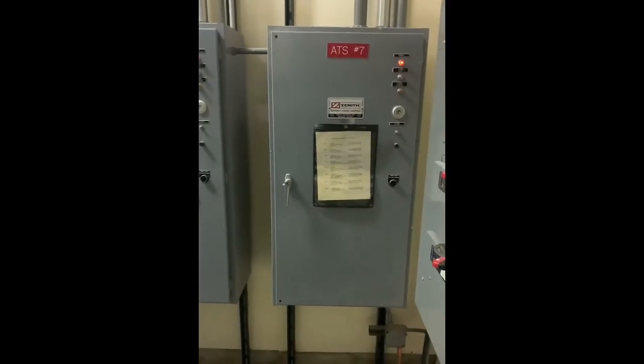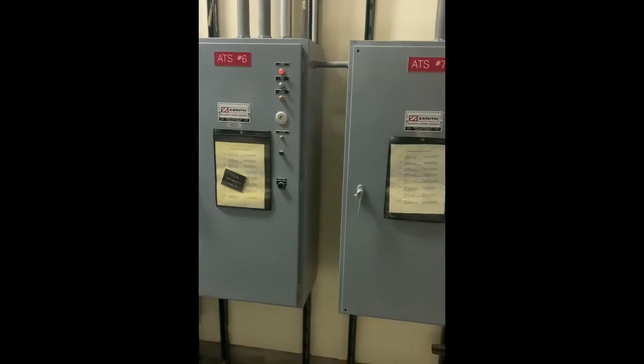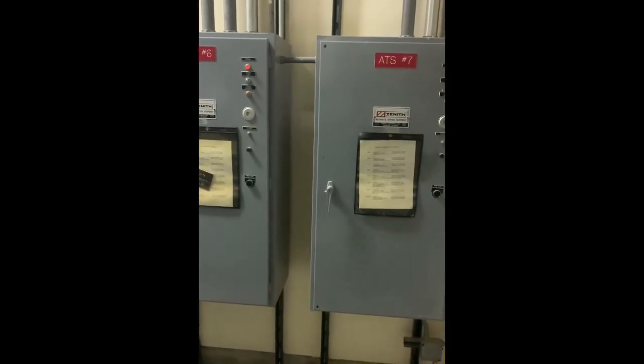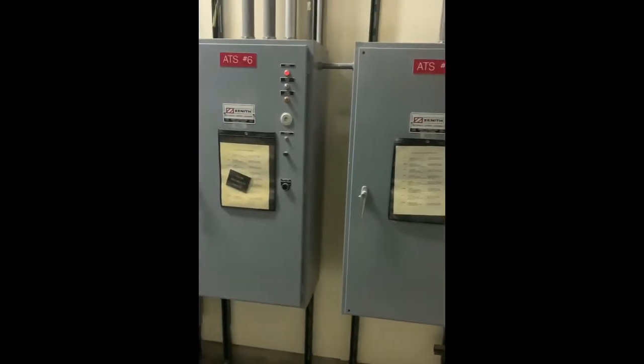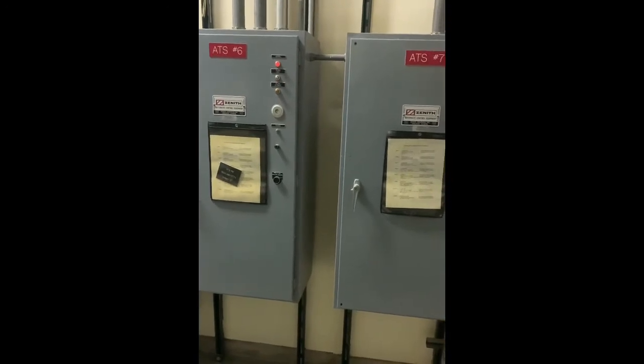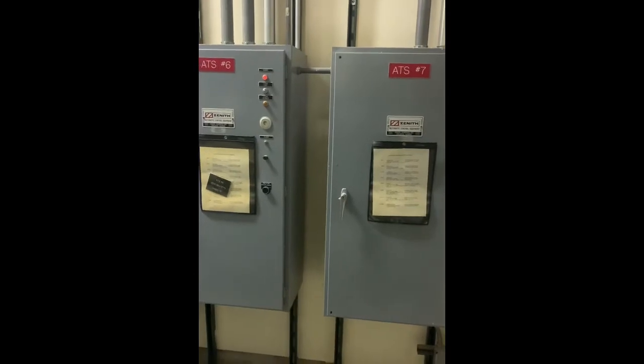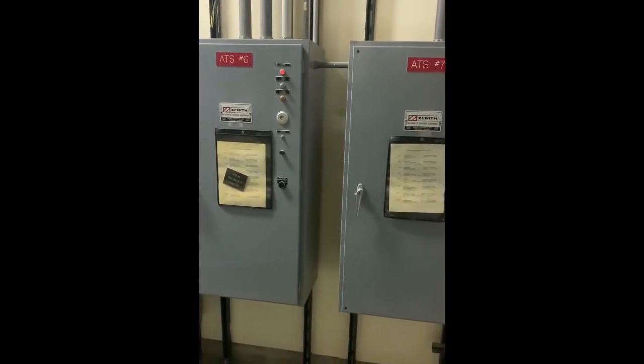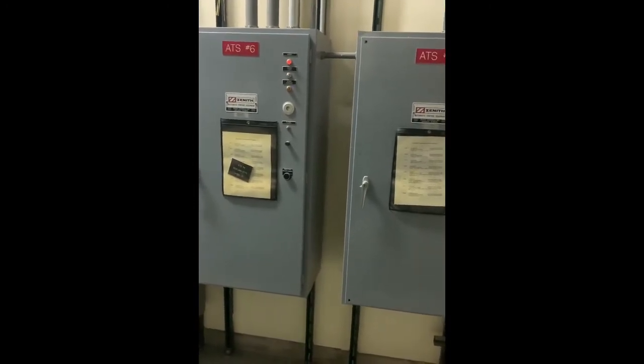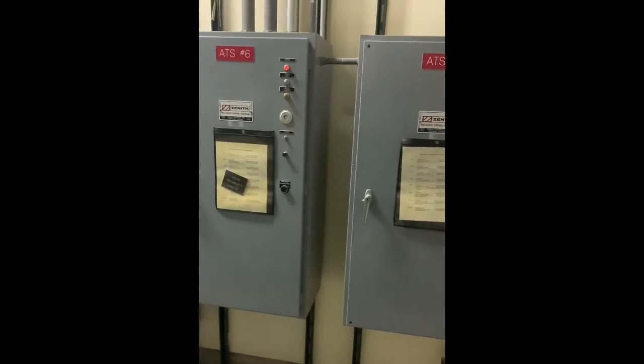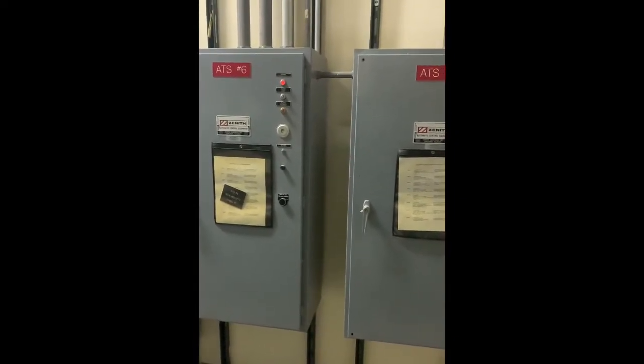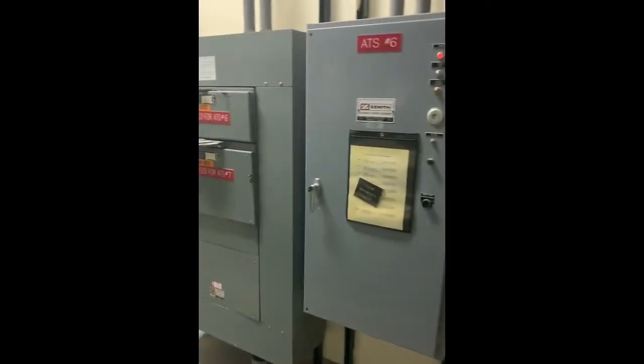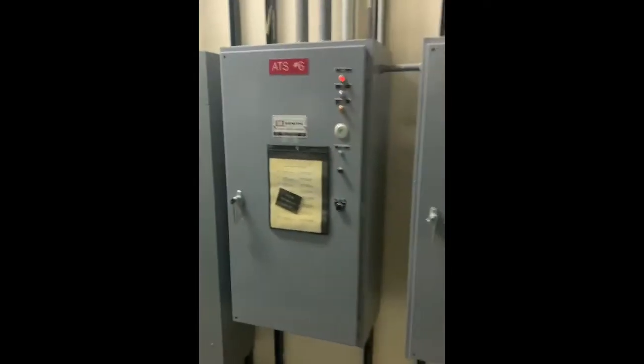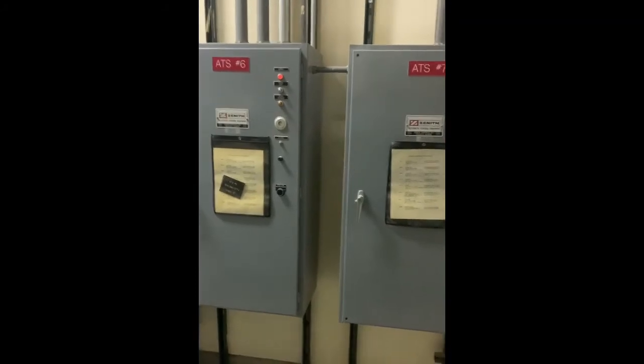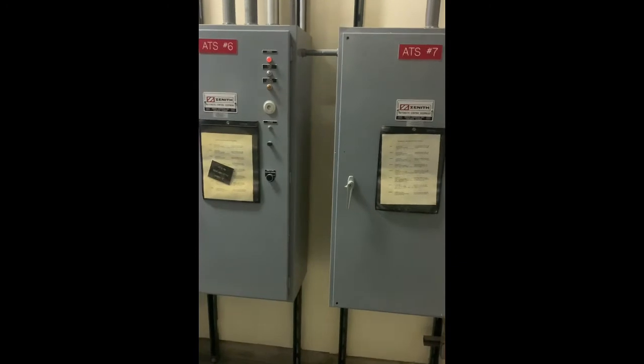Transfer switches can be standalone units such as these that you're seeing here. They could also be integral devices mounted within the switchgear, switchboards, or panelboards as part of a building's distribution system. Transfer switches can come in a couple different configurations. These are open transition, which means they are break before make. They will not close until they open up from the utility power source. Another type is a closed transition, which is make before break, where it will close while it's still connected to the utility feed. There are also certain situations where you could have a parallel feed. You could be feeding from your generator and ComEd utility at the same time.